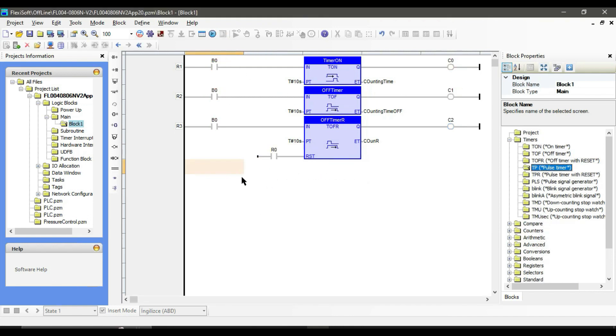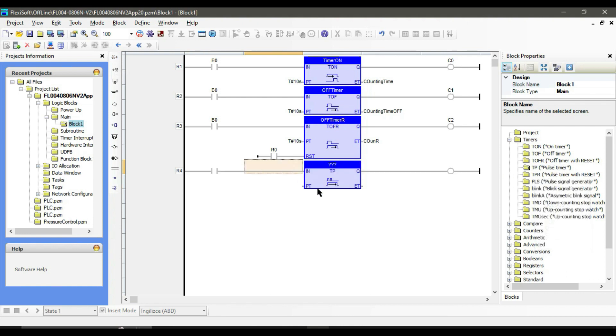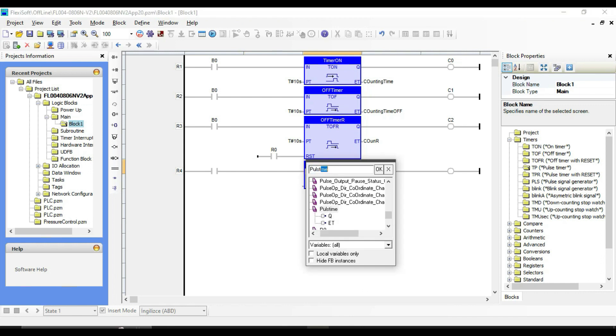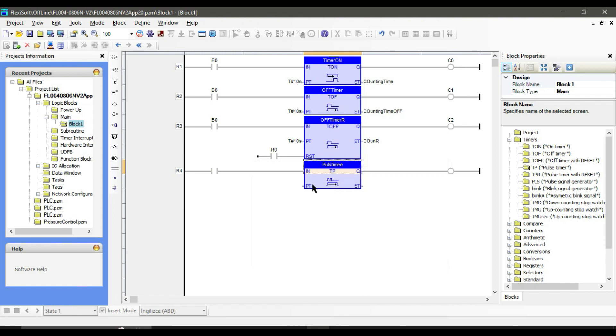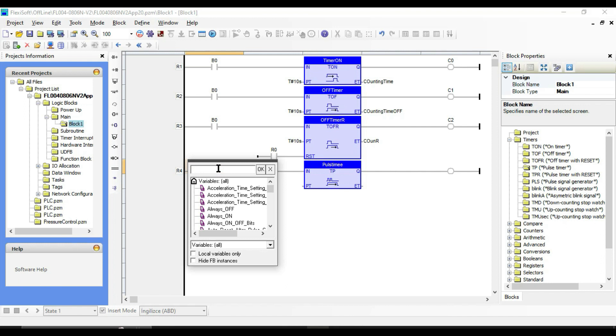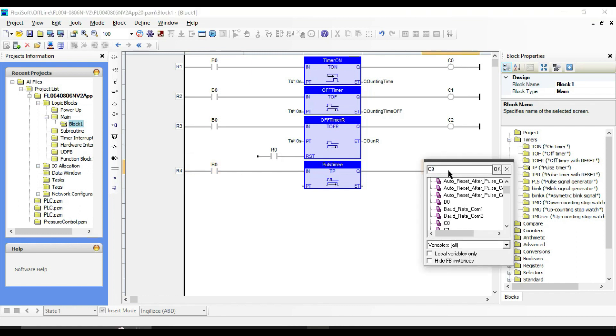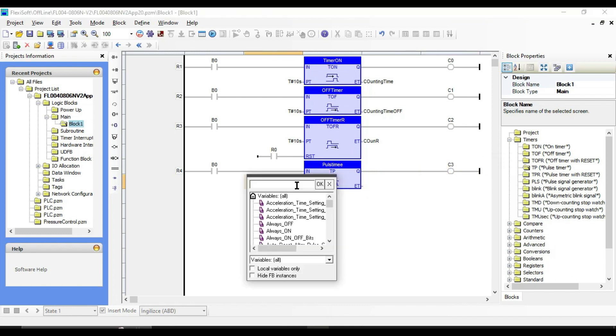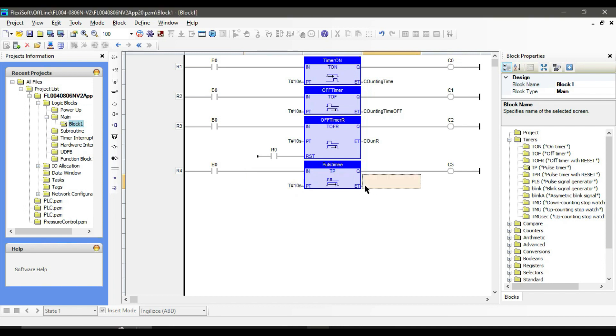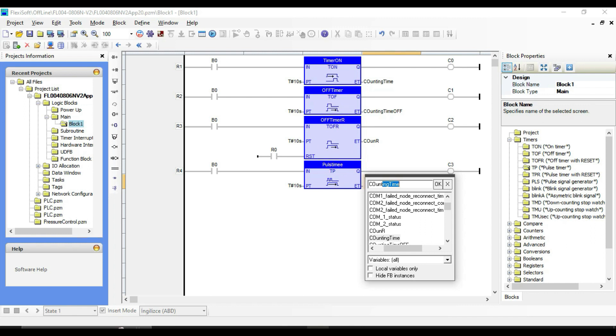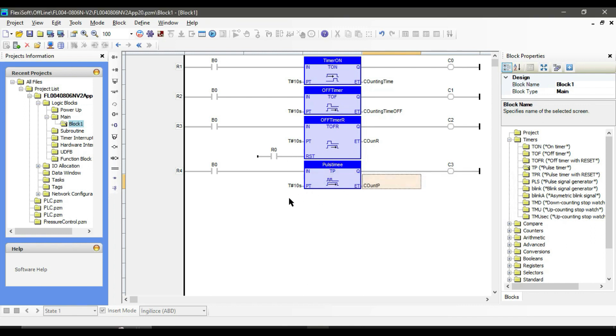Next we have TP, or pulse timer. The pulse timer generates a pulse of a specific length of time. The function block has four pins: one input which takes a boolean data type, one output which also takes a boolean data type, a preset time which takes a time data type, and an elapsed time which also takes a time data type. The PT or preset time is the length of our pulse, and the elapsed time is how long the pulse has been activated.